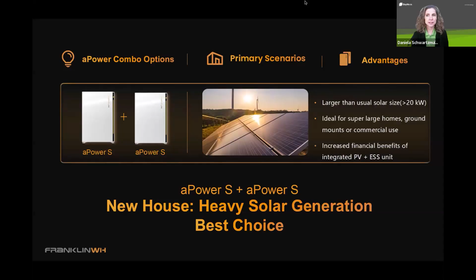They're essentially synonymous. For the rapid shutdown requirement, you could have some type of optimizer or just an MCI, a mid-circuit interrupter, where you're just going to kill the PV on the rooftop. Our device is going to be MCI style, only for the rapid shutdown requirement—there will be no optimization or monitoring from that device specifically.